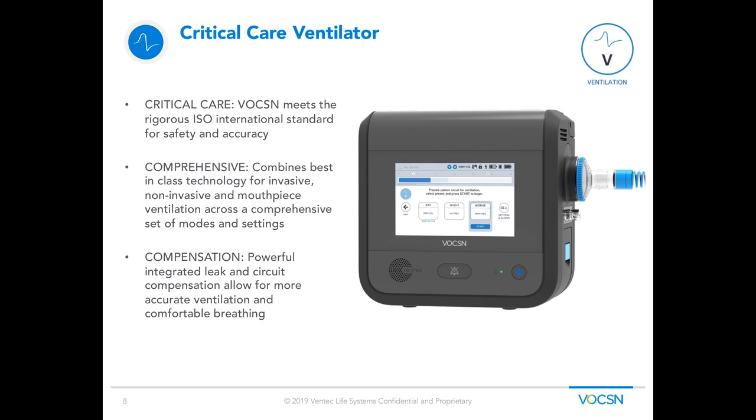When we talk about the V portion of VOCSN — the ventilation portion — we're talking about a critical care ventilator. VOCSN meets the ISO standard for critical care, meaning it needs to accurately deliver ventilation breaths, both volume and pressure, over a bell curve, hitting over 3,200 data points in extreme conditions and temperatures. The modes of ventilation that VOCSN provides are comprehensive — all your traditional invasive, non-invasive, and mouthpiece modes of ventilation. VOCSN's algorithm also has a powerful leak compensation that allows delivery of accurate ventilation in one comfortable breath.